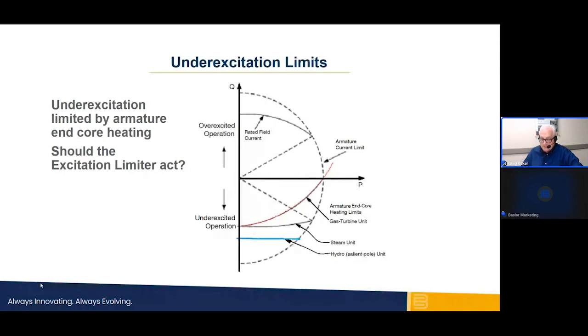The loss of field condition is similar and will, in most cases, result in the machine being tripped, disconnected from the utility bus. Operating underexcited is acceptable and sometimes required for stable grid operation. There are conditions of elevated voltage level that present an urgent need for the synchronous machine to absorb, to act as a load for the reactive power from the utility lines or the other parallel connected synchronous machines.